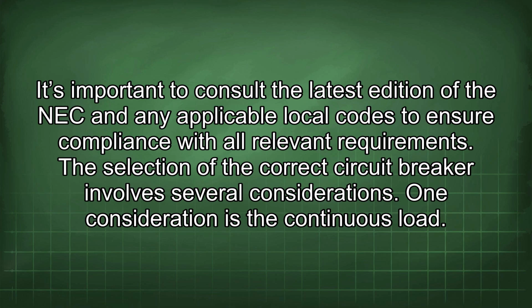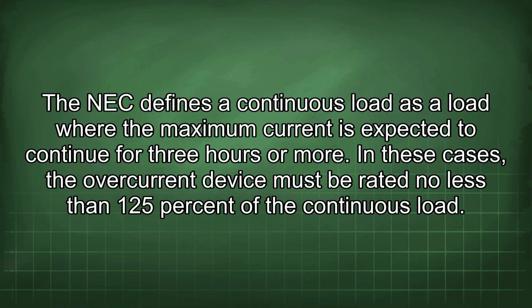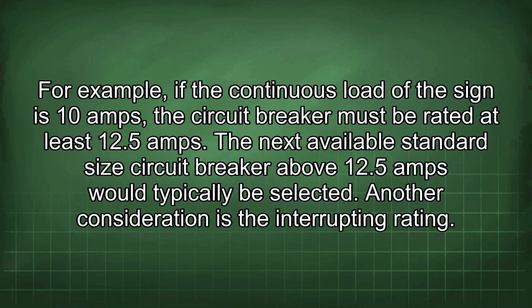One consideration is the continuous load. The NEC defines a continuous load as a load where the maximum current is expected to continue for 3 hours or more. In these cases, the overcurrent device must be rated no less than 125% of the continuous load. For example, if the continuous load of the sign is 10 amps, the circuit breaker must be rated at least 12.5 amps. The next available standard size circuit breaker above 12.5 amps would typically be selected.